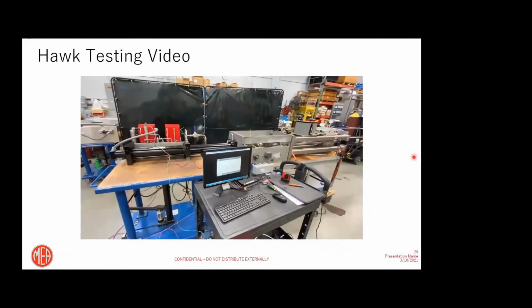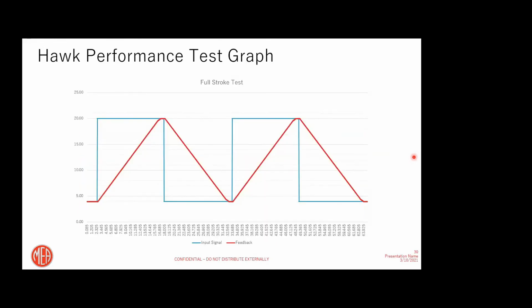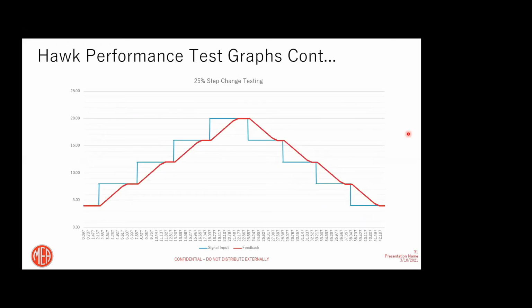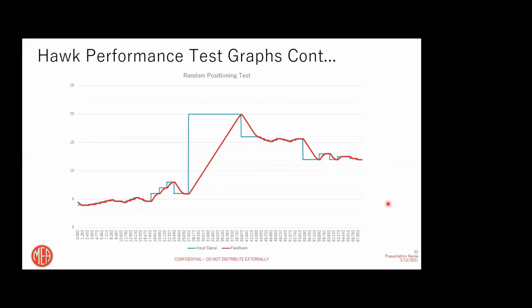So basically here you see the video of our random testing, just to show you exactly what we did here. And of course, we plotted all the performance test data, and this is a full stroke speed test. As you can see, it started from 4 milliamp, went to 20, basically with 0 overshoot, right into the dead band, and just goes back and forth. Additionally, this is the same 25% step change testing. We tested it, and you can see that it hits right in every time and follows the curve. Additionally, the one that you saw in the video, we simulated a random signal. It just follows it back and forth, and as you can see, it follows it very clearly and properly operates this actuator valve.